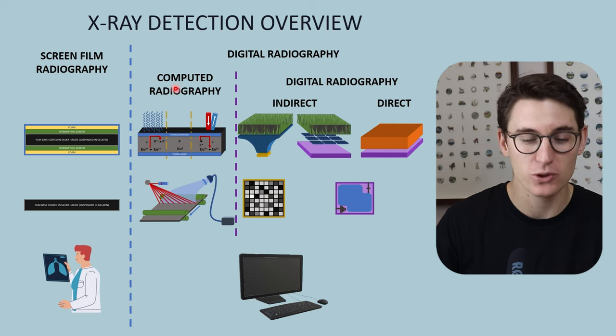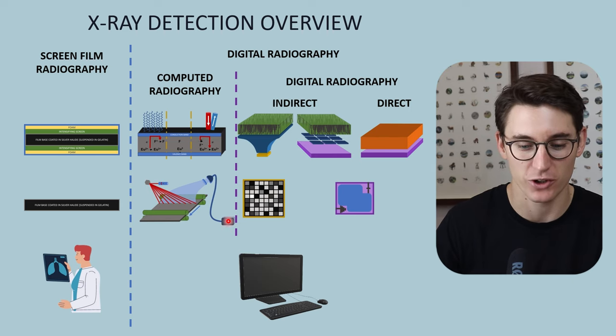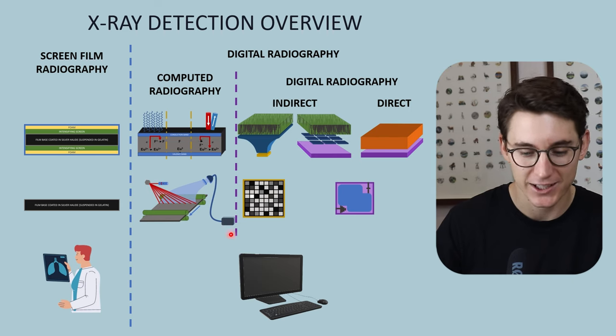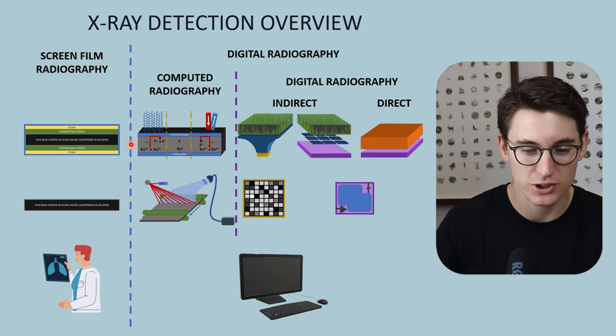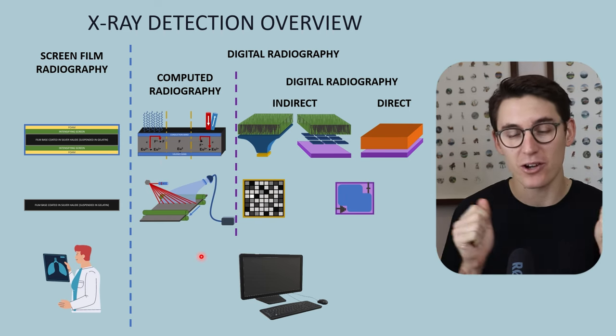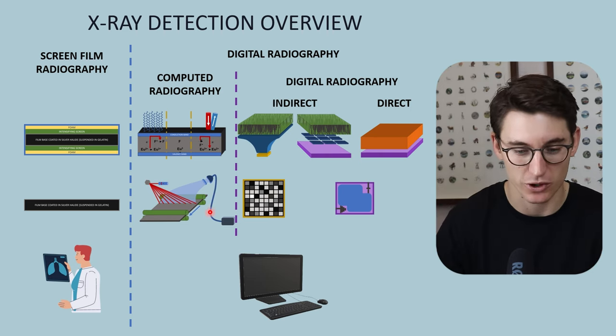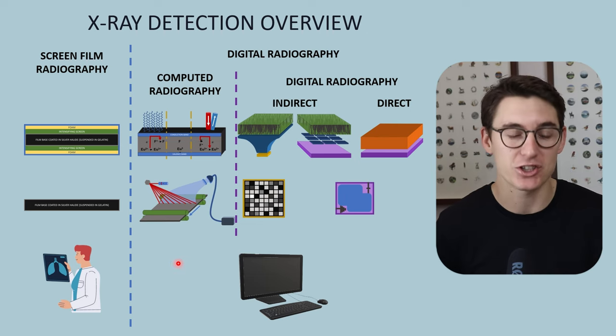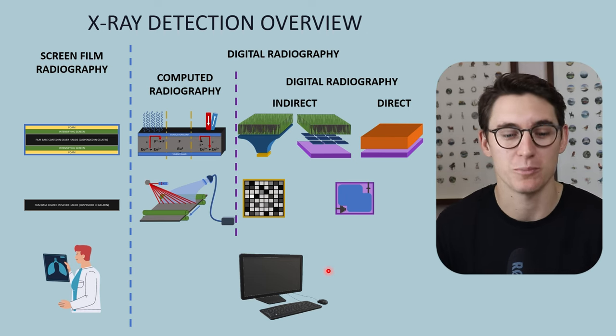In computed radiography, up until the final step everything is analog. We use a manual process, and at the last moment we use an analog-to-digital converter to convert the analog signal into a digital signal to create our digital image. Computed radiography uses a cassette-based system — we can carry that cassette for many months after taking the radiograph prior to processing it and digitizing the image, unlike digital radiography systems where a digital image is created almost immediately.